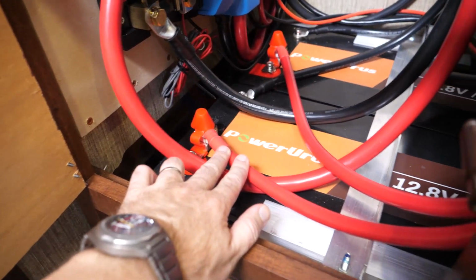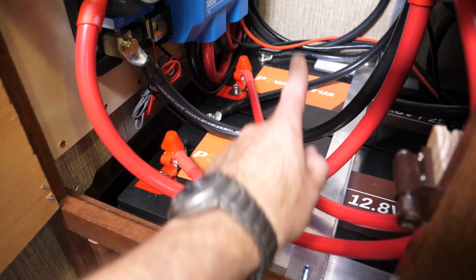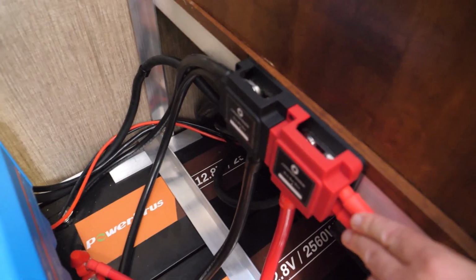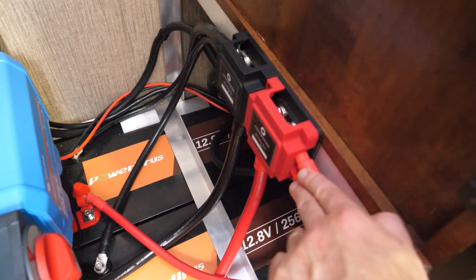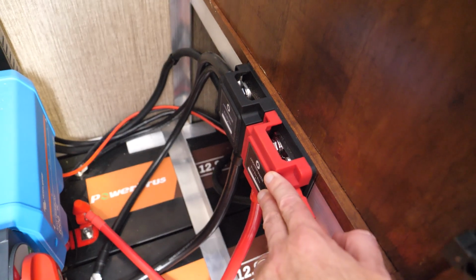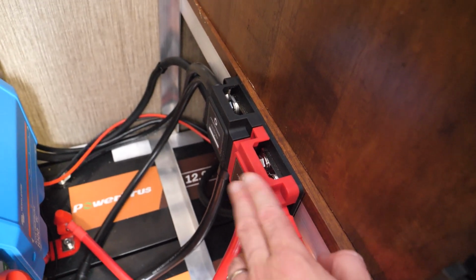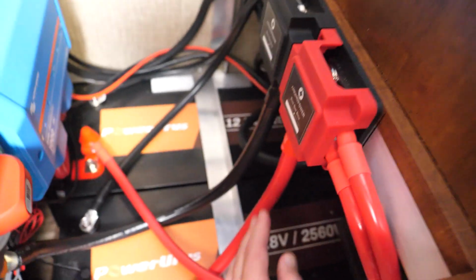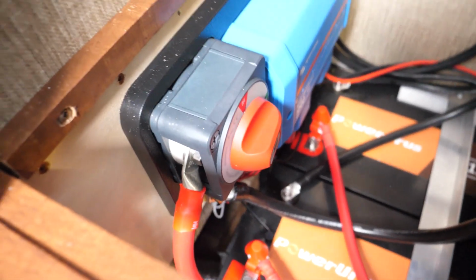Those smaller wires are carrying the current in parallel. I've got two positives going from the positive of each battery, and two negatives in the back, and they come up together into a little cheap off-the-shelf bus that I found. So the smaller wires go to this junction box, or bus bar setup, and from there they're combined into these two larger 4-aught cables that feed the rest of the system.